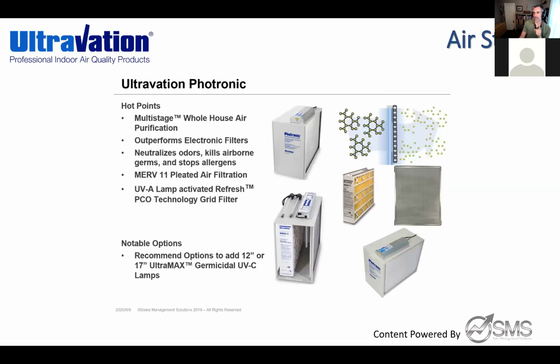Earlier I talked about UVA versus UVC. This is a long-standing product we didn't really promote before, but now a lot of people are talking about electronic air purifiers—does your box click or make a static sound? We've always had something that doesn't make the clicks or sounds, because we focus on UV light. UVC wavelength light can be dangerous to a filter; over time it will break down the material. So in this box we don't put UVC lamps because of the closed, contained area. But we wanted to create a way to add PCO into a filter box if somebody hasn't done equipment solutions, or if they're just trying to add more purification.